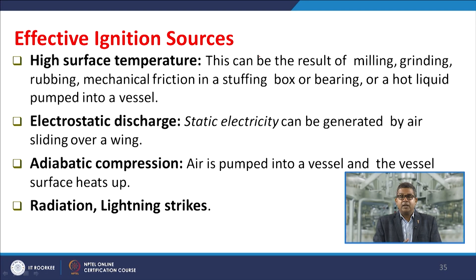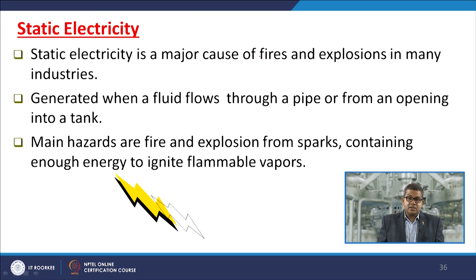Then there is a chance of static electricity. It's a major cause of fire and explosion in many industries, and is generated when fluid flows through a pipe or from an opening into a tank. The main hazard is fire and explosion from a spark containing enough energy to ignite the flammable vapors. So you must know that if there is any chance of generation of static electricity, the system must be properly grounded, bonded, etc. We will discuss this in subsequent modules.